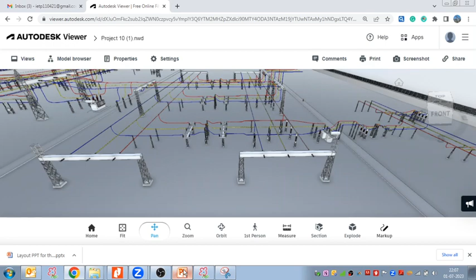So the same planning and orientation we have explained here in the text. The transformer bay orientation should be towards the downside voltage level of the substation, and that we have already discussed. So we discussed two bays, the line bay and the transformer bay, and now coming to the common bus bar. The common bus bar will be placed at right angles, meaning 90-degree angles to the feeder.